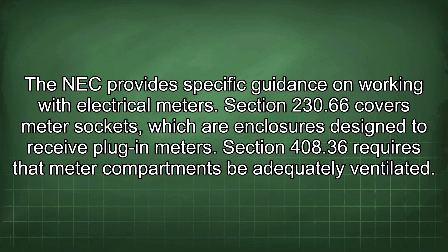Section 230.66 covers meter sockets, which are enclosures designed to receive plug-in meters. Section 408.36 requires that meter compartments be adequately ventilated. Section 225.30 limits the number of supplies to one building or other structure.